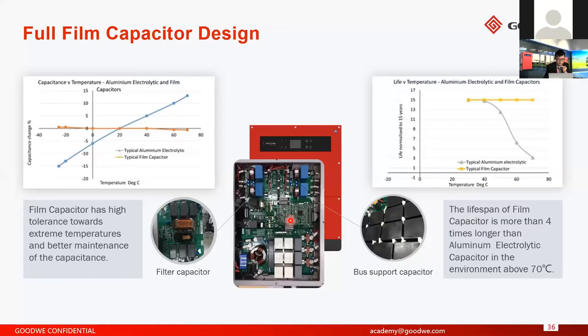We only use a film capacitor. We don't use an electrolytic capacitor inside, because the lifetime of the film capacitor is much longer than the electrolytic capacitor, especially in hot weather. So for the Indian market, the customer needs to pay attention to these components inside, because if the inverter is integrated with an electrolytic capacitor, the lifetime will decrease a lot in hot weather.